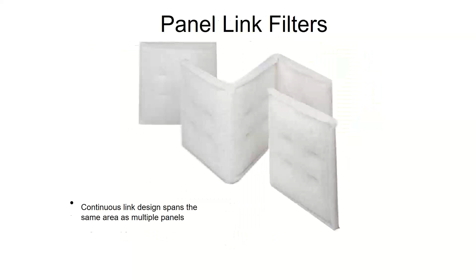Another way to get that done, I don't have a good example on here, do I? No. I should put a picture on here. I didn't do that. You can't really see on these ones, but there are pleated filters, right? So a pleated filter, if I draw a crappy drawing of it, I should put a better picture on here. Inside the actual filter, inside this cardboard holder of the filter, the media goes in a pattern like that, all right? So we call that a pleated filter. It's basically like putting those little V-banks into the actual filter. So on small equipment, I will want to put pleated filters in to get that surface area to do a better job of catching stuff. Or even on big equipment, I could put pleated filters in and have the V-bank and have both of those things working in my favor.